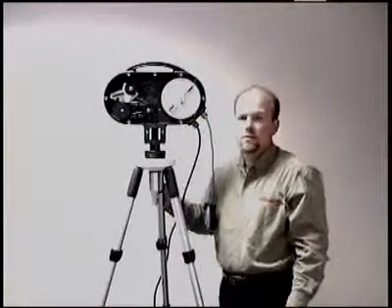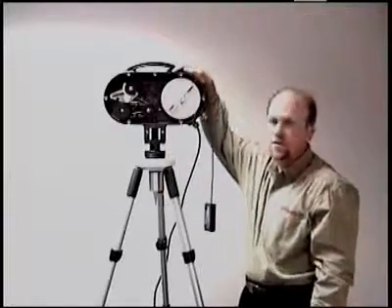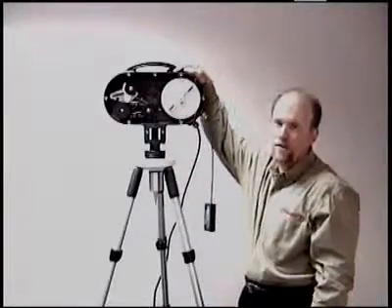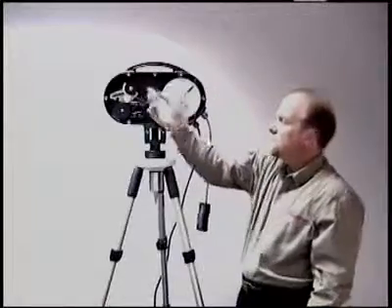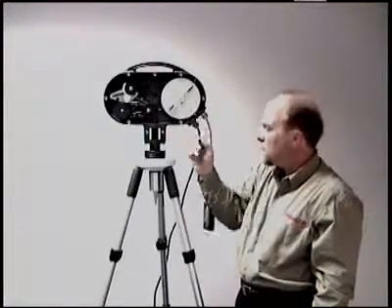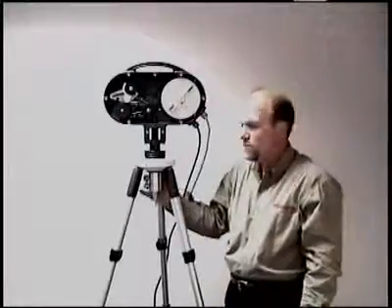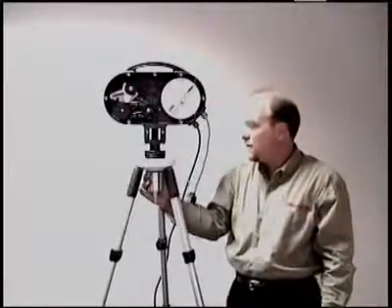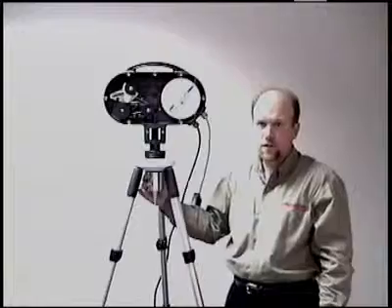Here's how SmartBob 2 works. An SBR2 remote sensor is mounted on top of the vessel. A motor releases stainless steel cable from a supply pulley which causes a weighted sensor probe to quickly drop from the top of the vessel to the surface of the material.